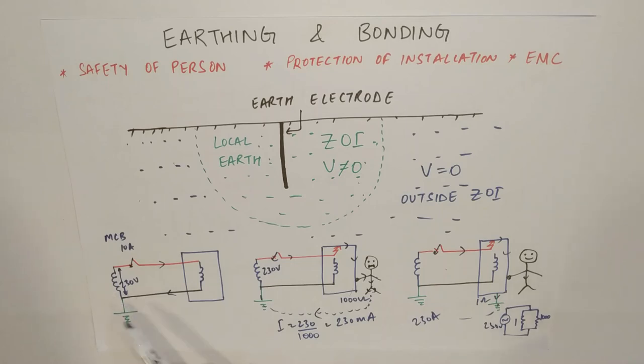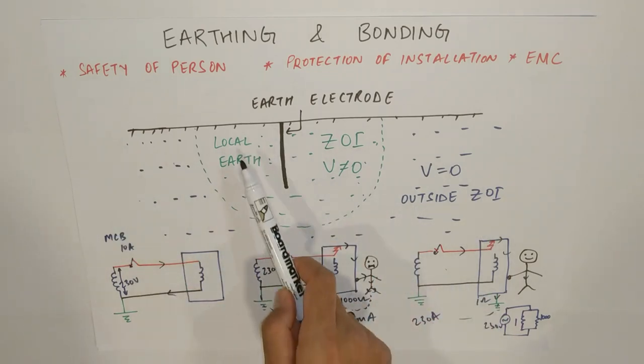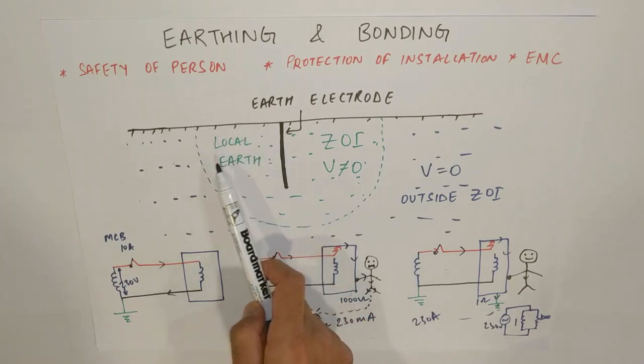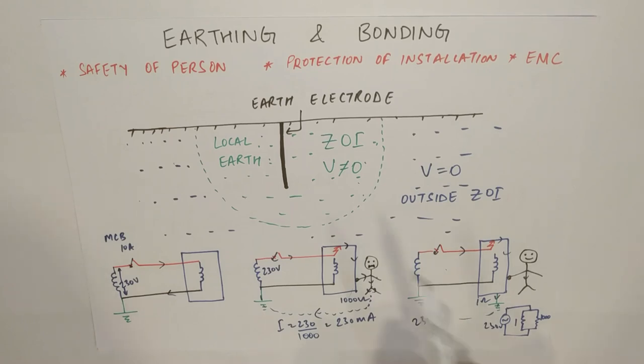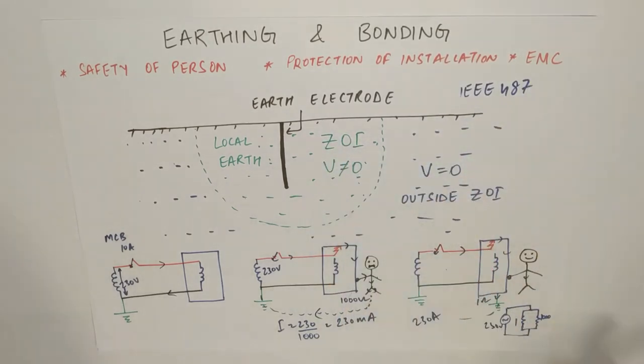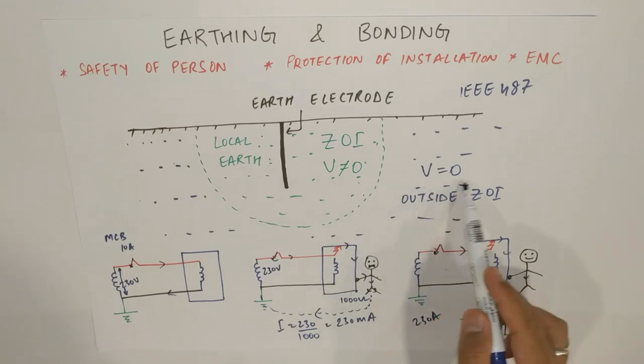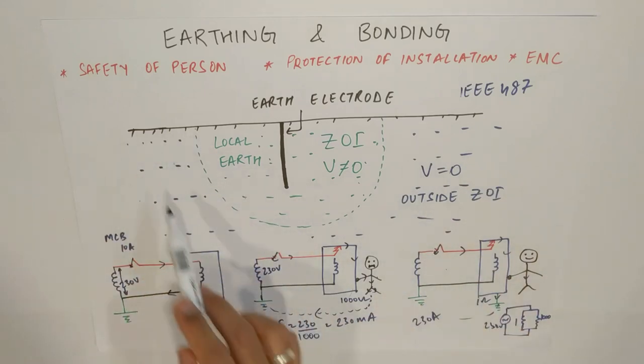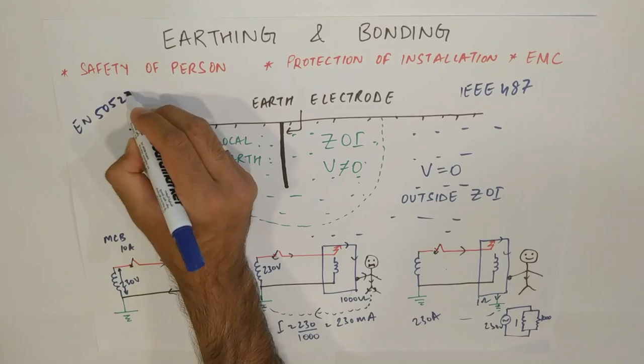Now, as this is an earth electrode. What is it? It is nothing but a conductive part which is embedded inside the earth to have an electrical contact with this earth. What is local earth? Local earth is the region or the part of the earth which is near to this electrode and which is having a potential not necessarily equal to zero. It can be, but mostly it is not. This region is known as zone of influence. To have a more feel of it, you can refer to IEEE 487 for the definition of ZOI. And the region outside this zone of influence, which is conventionally taken as voltage zero at this region, is known as remote earth or reference earth. This blue region. These definitions are provided for local earth electrode in EN 50522. I have taken the reference from them.